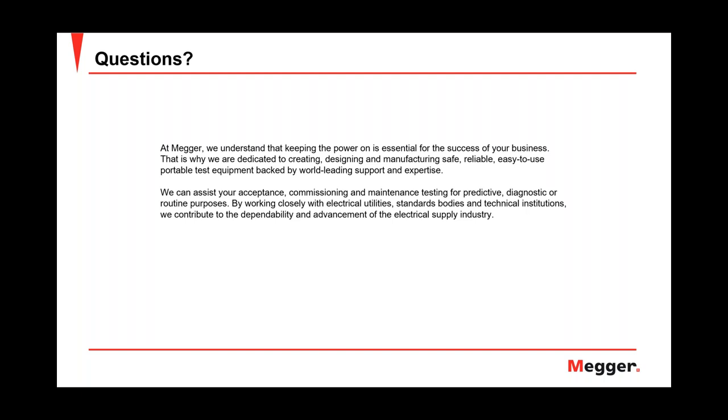Absolutely. Thank you, Michael. The difference between sheath testing and insulation resistance testing, let's say we're using an integrated unit like the Smart Thump or the Easy Thump: sheath testing is a method used for performing sheath fault testing on the concentric neutral or sheath of that cable. The same method can be employed to test secondary cables as well. Essentially, it limits the maximum voltage output of the unit, because with a sheath fault, the insulation is actually the jacketing of that medium voltage cable, which is rated at a much lower voltage than the insulation internal to the medium voltage conductor.